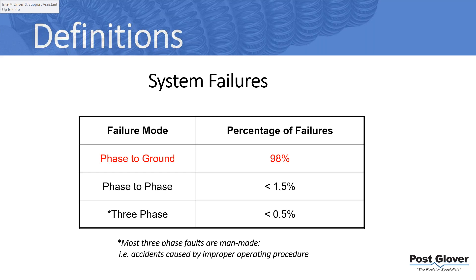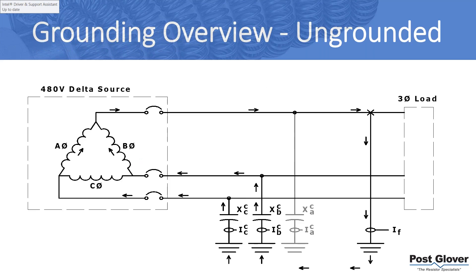Phase-to-phase faults are much less likely to occur on a resistance ground system from a single line-to-ground fault than on a solid ground system. Three-phase faults are a very small percentage — usually a man-made issue. I'm going to do a comparative analysis because resistance grounding is kind of in the middle, a hybrid of an ungrounded system and a solidly grounded system. It tries to take the best of both situations.